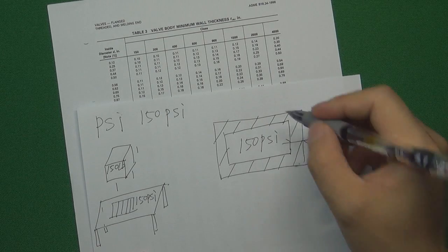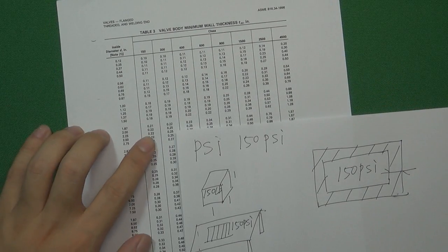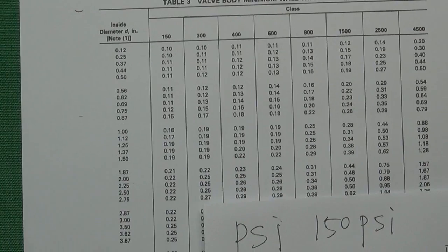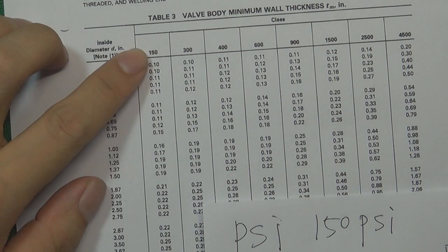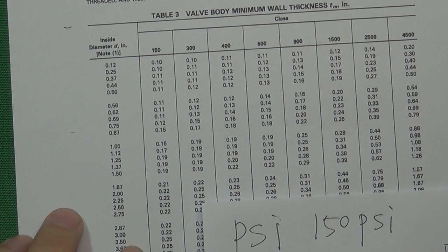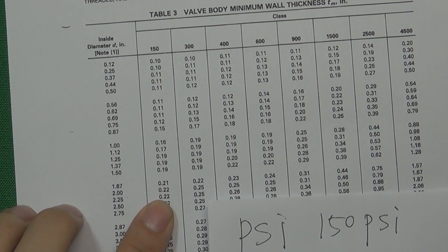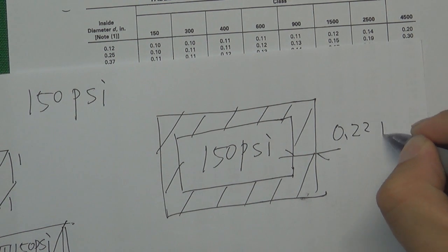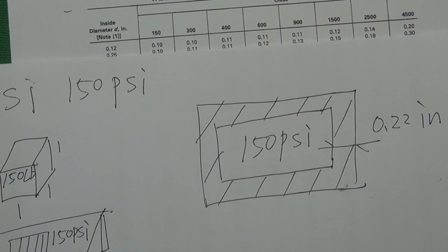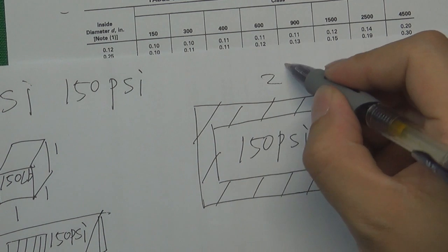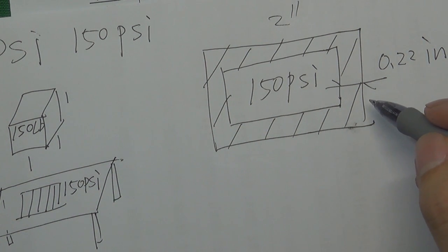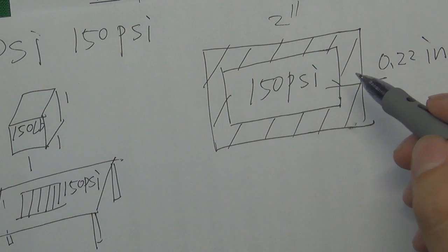So how thick does it need to be? For example, this valve is 2 inch, and the pressure class is 150. According to the valve body wall thickness table, we need at least 0.22 inch of valve wall thickness to hold the pressure. So this 2-inch valve with 0.22-inch wall thickness can hold 150 psi pressure inside.